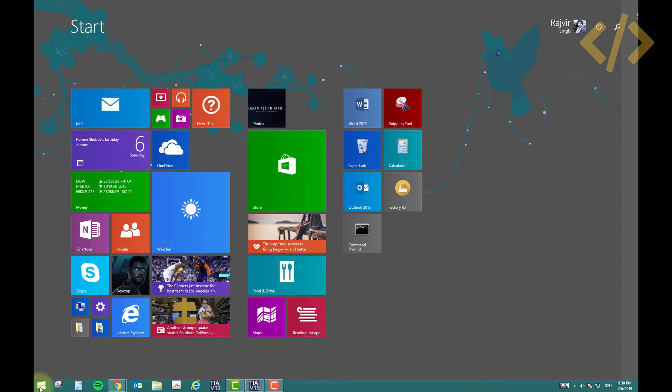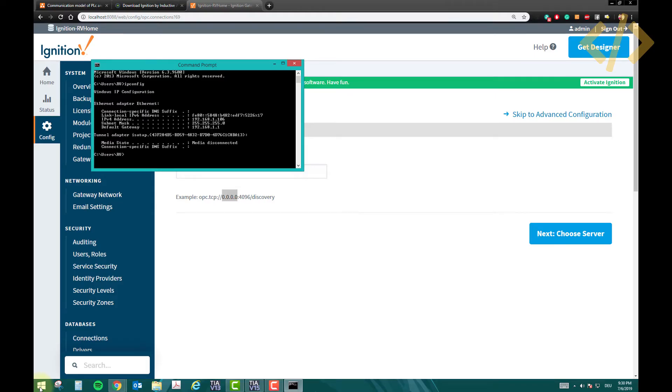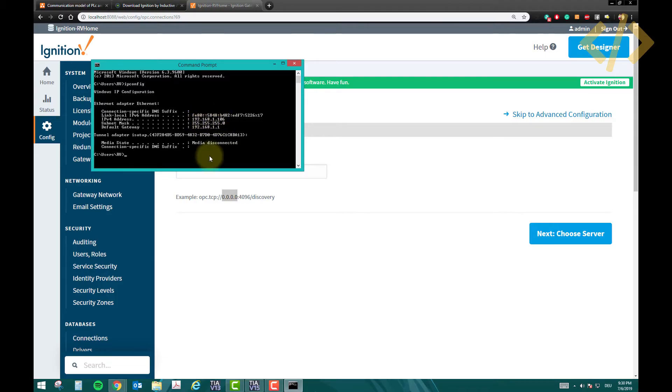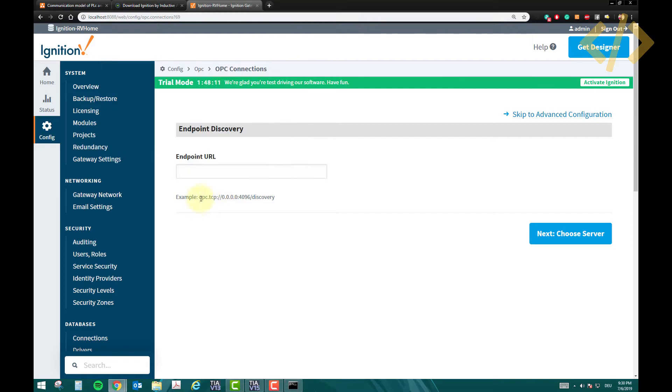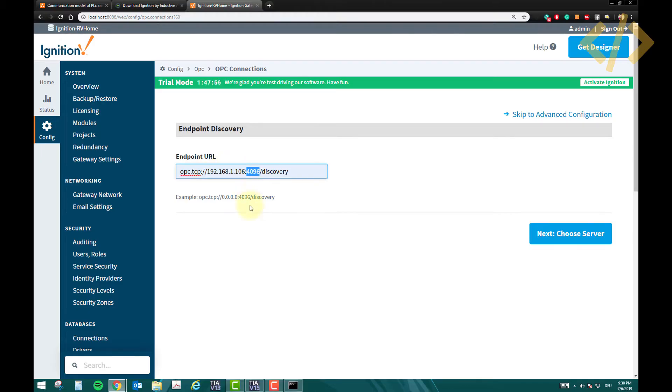As I told you, if I show you my card address, it's 192.168.1.106, this is the IP address of my ethernet card. So I have to use the same syntax, opc.tcp. So if I show you here, I have used this before. Notice here opc.tcp://192.168.1.106, that's my IP address, and that's the port address. So let it be 4096 by default /discovery.